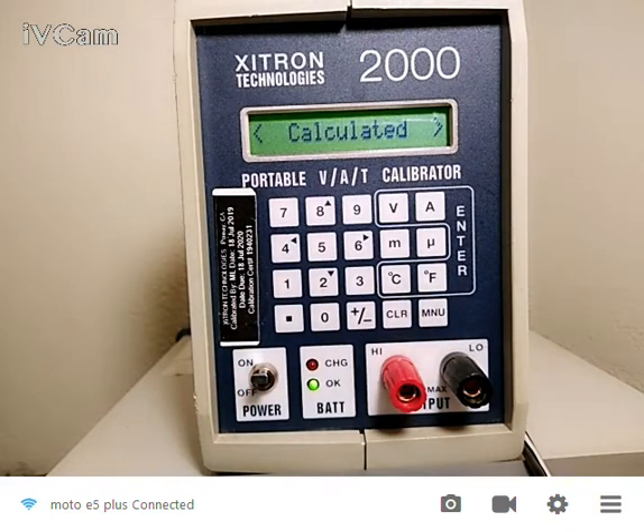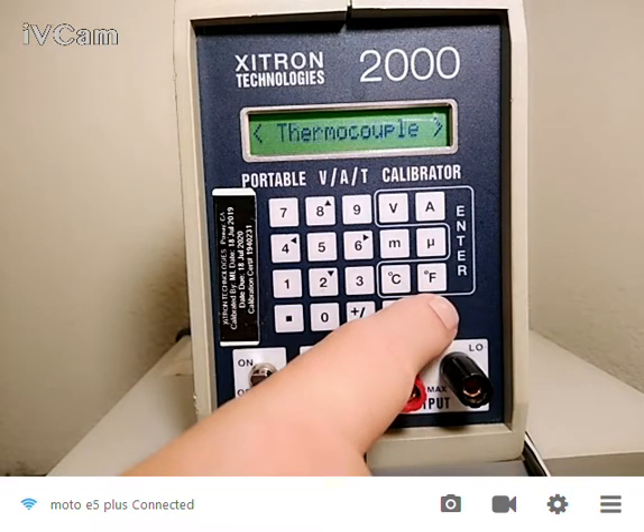Calculated allows you to calibrate sensors, electronics for flow and pressure. It's basically linear interpolated, so you put in the endpoints and you say, I'm going to simulate a flow sensor that goes 0 to 500 feet per minute. And at 0, it's going to be this voltage, and at 500 feet per minute, it's going to be that voltage. After that, you can put in directly in feet per minute, and the instrument will do the calculations and output the correct voltage to emulate that flow sensor. So again, we can do that for pressure or flow sensors.